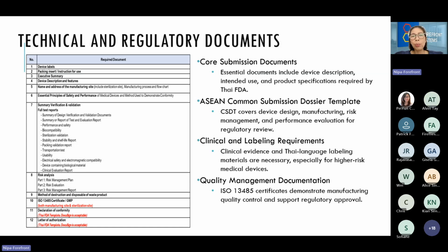Next, number 7 will be summaries of verification and validations. The full report has to be submitted. Then the next one will be the risk analysis file, and number 9 is the method of destruction and disposal of waste product. This can use the Thai FDA template. Then there will be the ISO 13485 certificate and the GMP. In case the product is a sterile product, the sterilizer certificate has to be submitted as well, right?